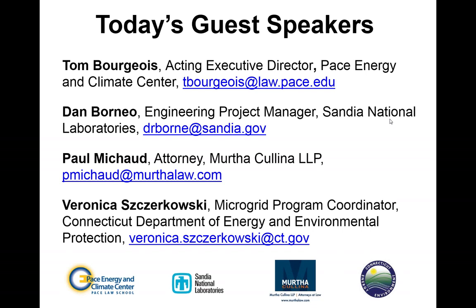Microturbines, once again, range from very small scale, but you can also gang them together or modularize them to multi-megawatt scale. So with CHP you can go from very small up to very large units, from micro CHP serving a household up to examples like Co-op City at almost 40 megawatts, Cornell University at over 30 megawatts, and the University of Texas Austin system at over 100 megawatts, running at 90% total system efficiency.